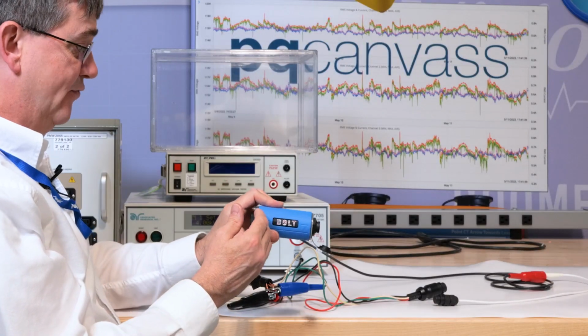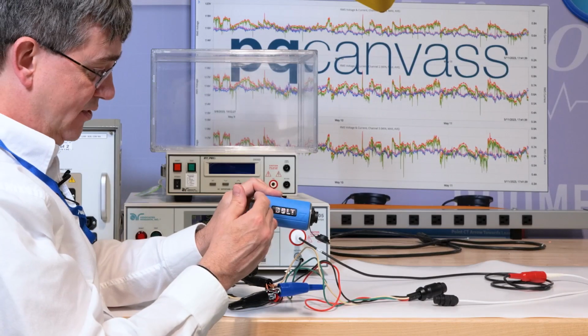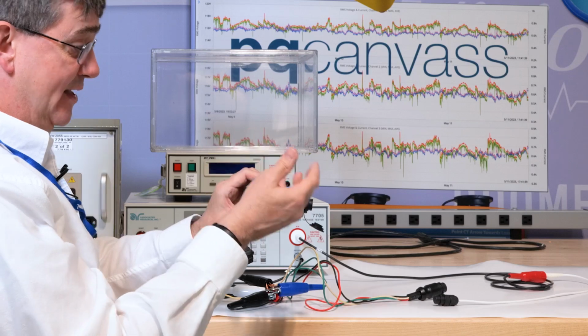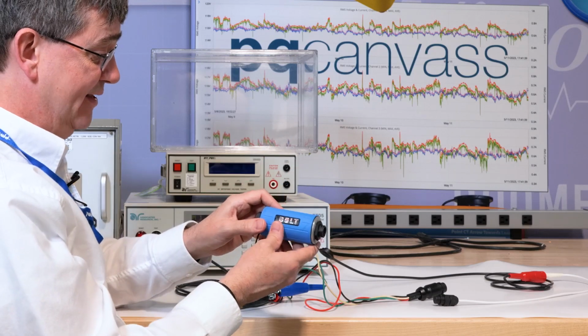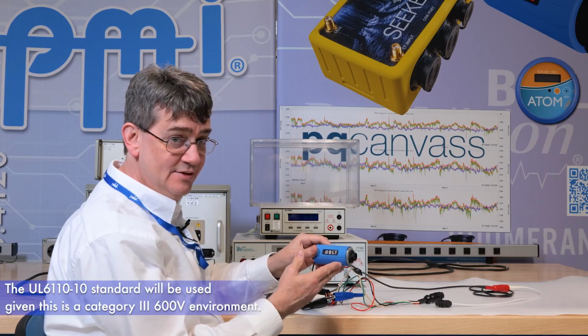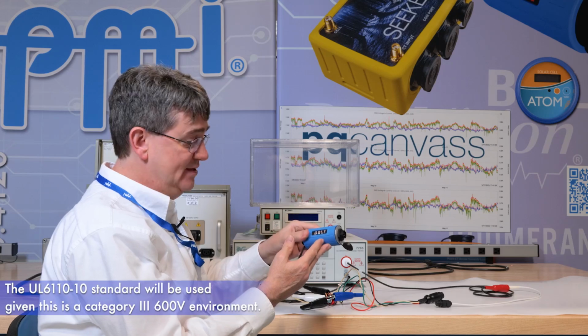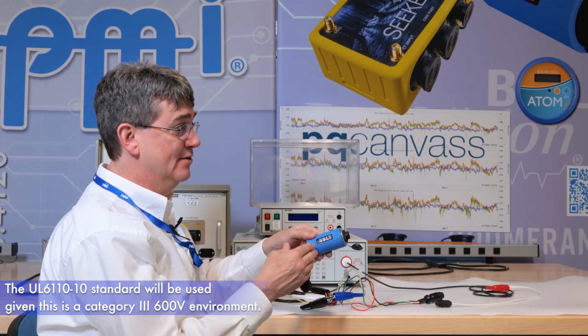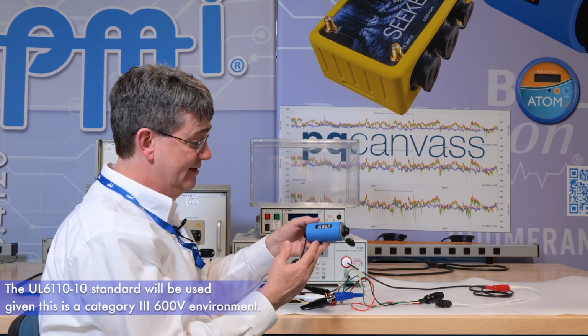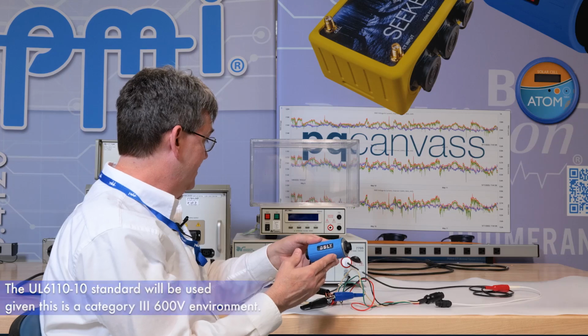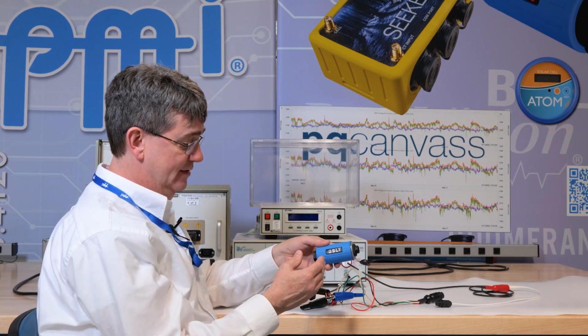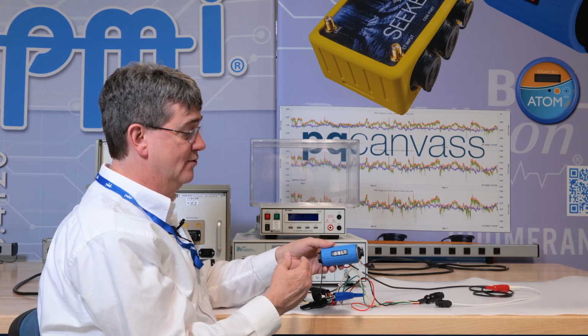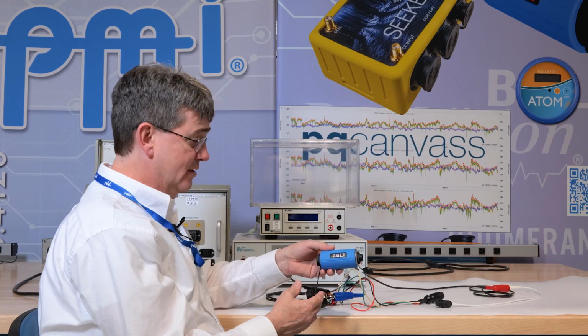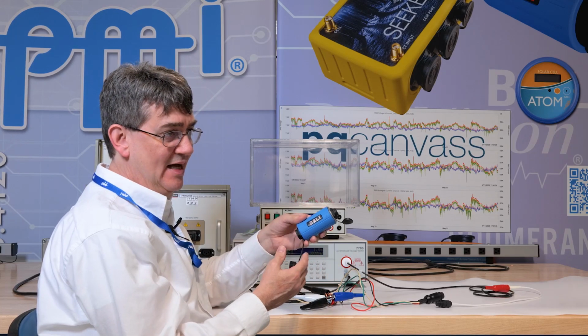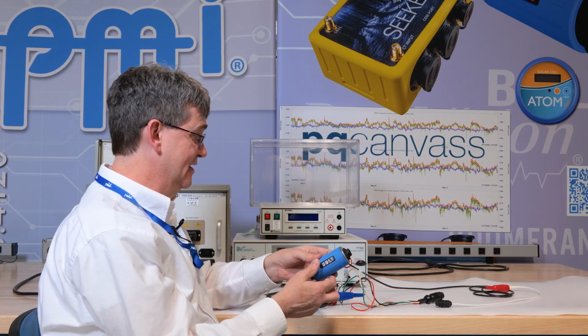We apply 4,000 volts across this bolt barrier, which is optically isolated, and we check to make sure there's no leakage current. We're testing in accordance with UL 61010, and because this is a category 3, 600 volt environment that the bolt can be placed in, that calls for a 4,000 volt test lasting 1 second across the barrier. The bolt is allowed a 0.5 milliamp leakage current during that test.